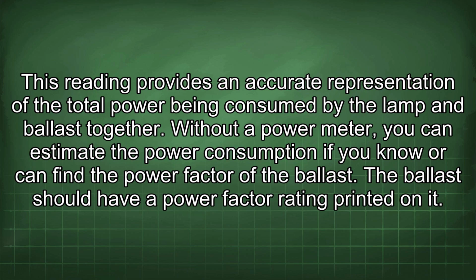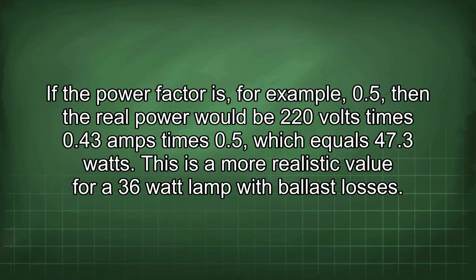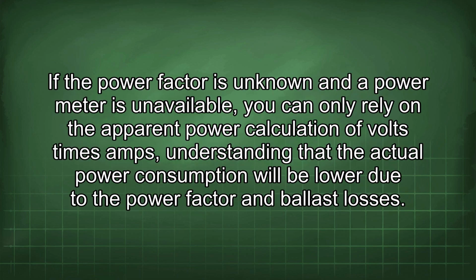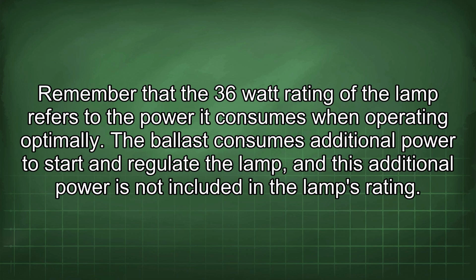Without a power meter, you can estimate the power consumption if you know or can find the power factor of the ballast. The ballast should have a power factor rating printed on it. If the power factor is, for example, 0.5, then the real power would be 220 volts times 0.43 amps times 0.5, which equals 47.3 watts. This is a more realistic value for a 36 watt lamp with ballast losses. If the power factor is unknown and a power meter is unavailable, you can only rely on the apparent power calculation of volts times amps, understanding that the actual power consumption will be lower due to the power factor and ballast losses. Remember that the 36 watt rating of the lamp refers to the power it consumes when operating optimally.